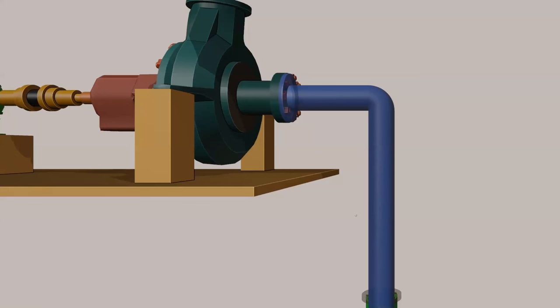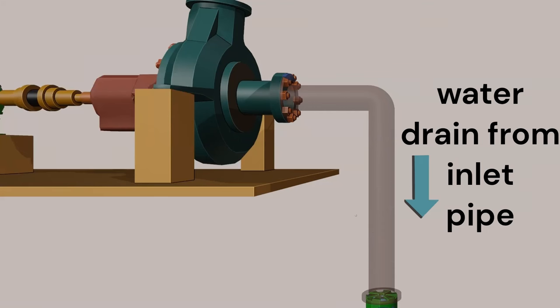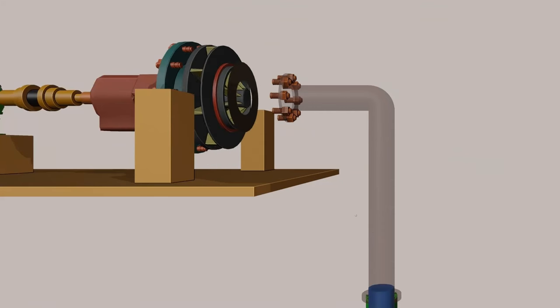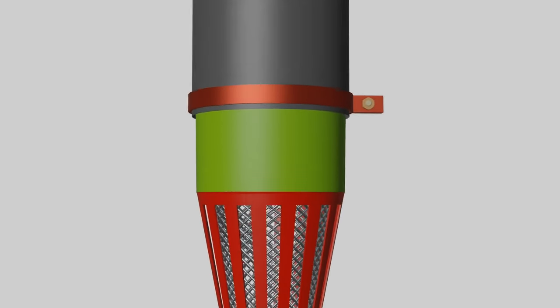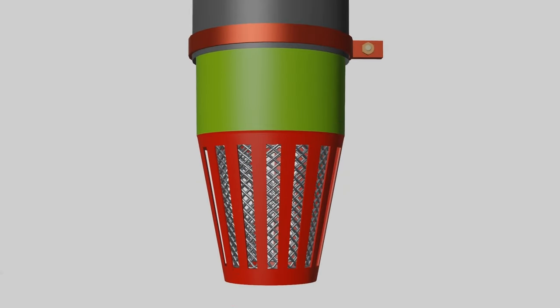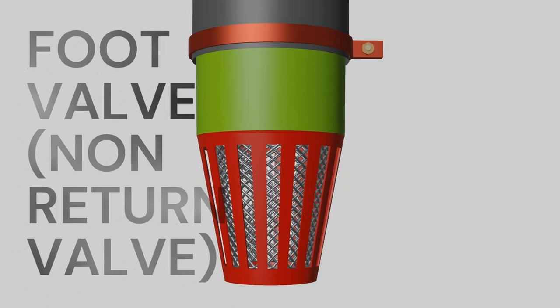If the pump stops working, the fluid drains from the inlet pipe. If we start the pump again, it struggles to suck fluid due to air trapped in the inlet pipe. To avoid that, a non-return foot valve is used to hold water in the inlet pipe.